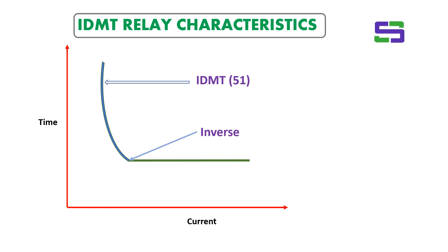For the IDMT 51 relay, up to the inverse point where the arrow is marked, this relay will behave with the inverse characteristic. It maintains an inverse relationship between time and current on the TCC curve. This inverse region may cover 20%, 30%, or 50% of the relay's range, depending on the relay manufacturer.